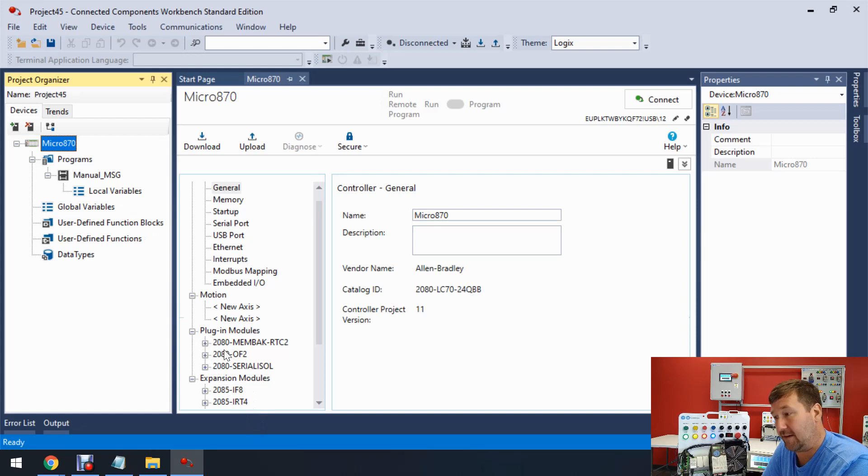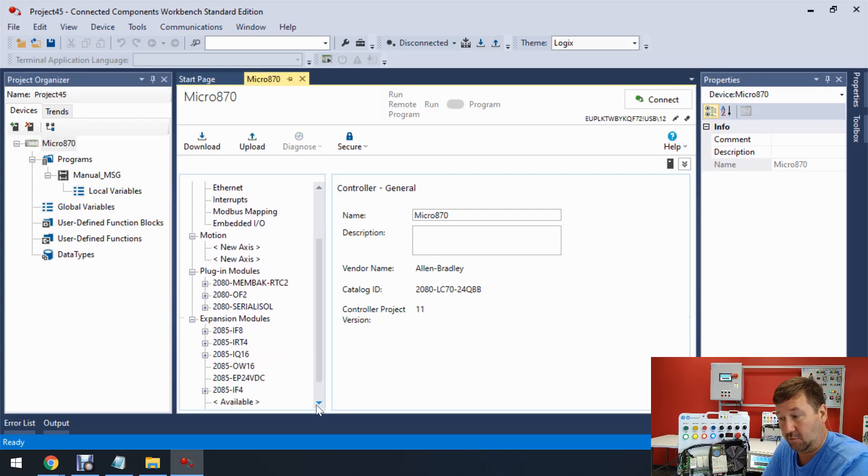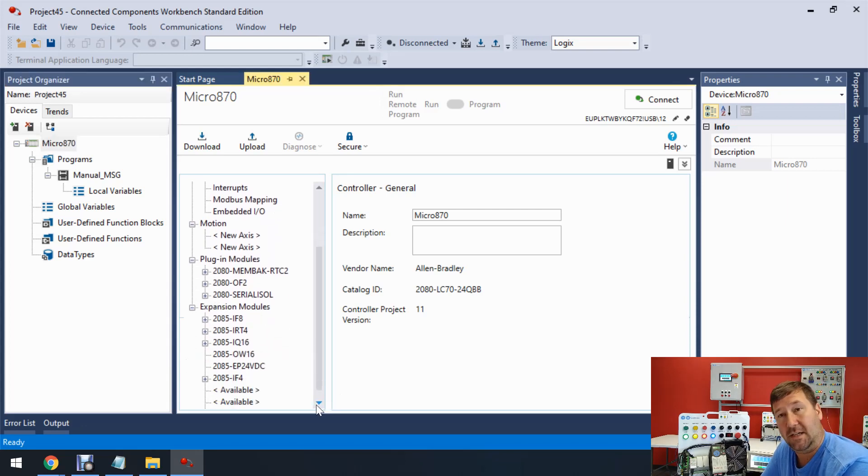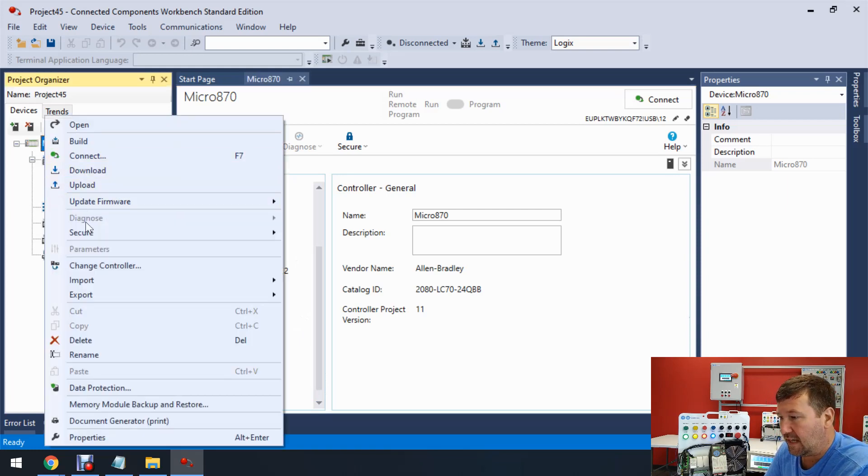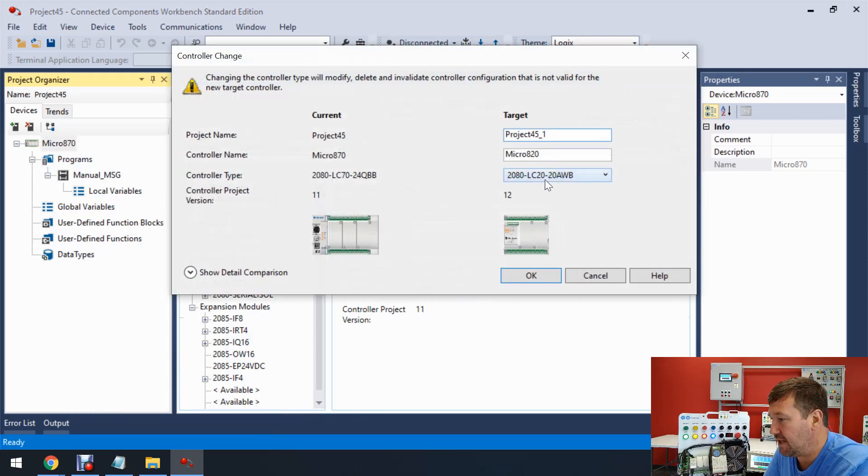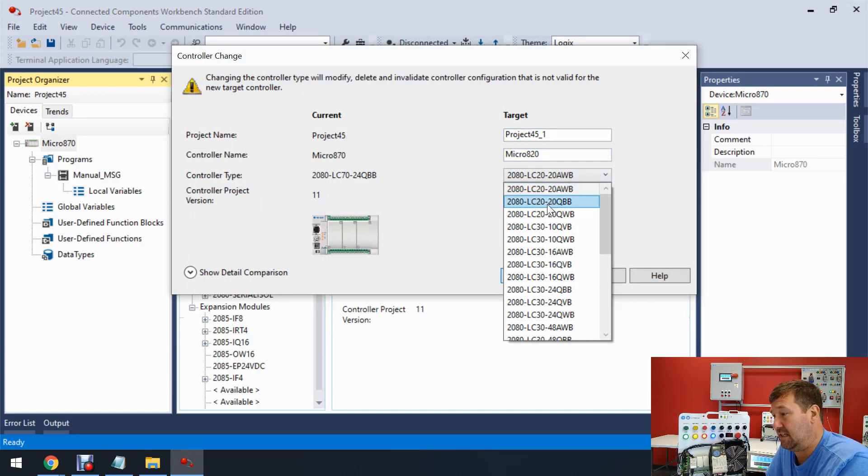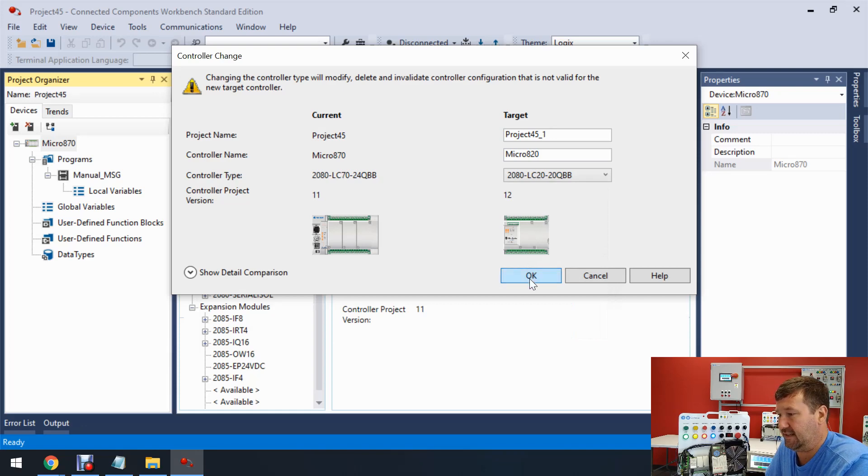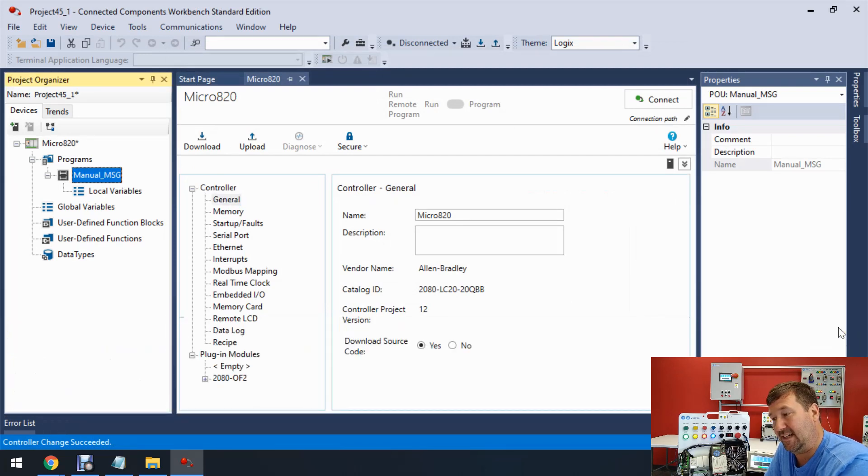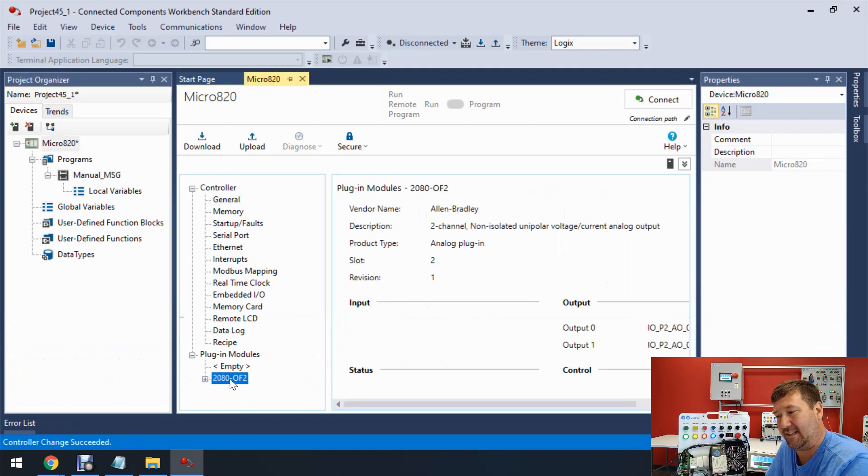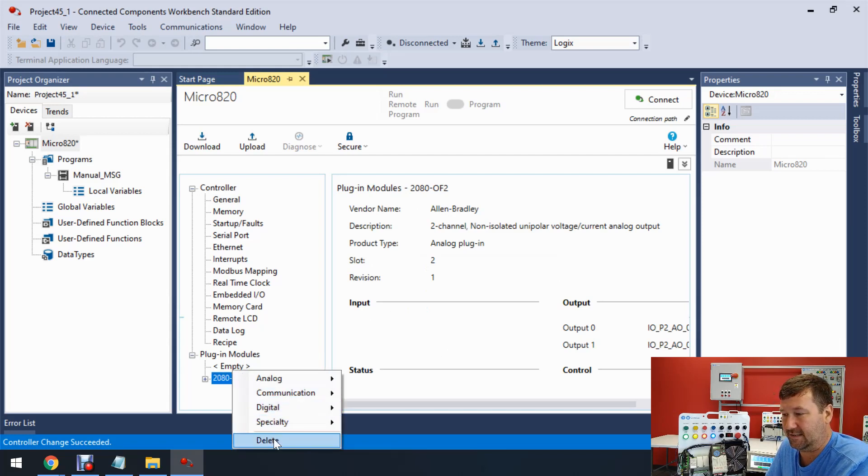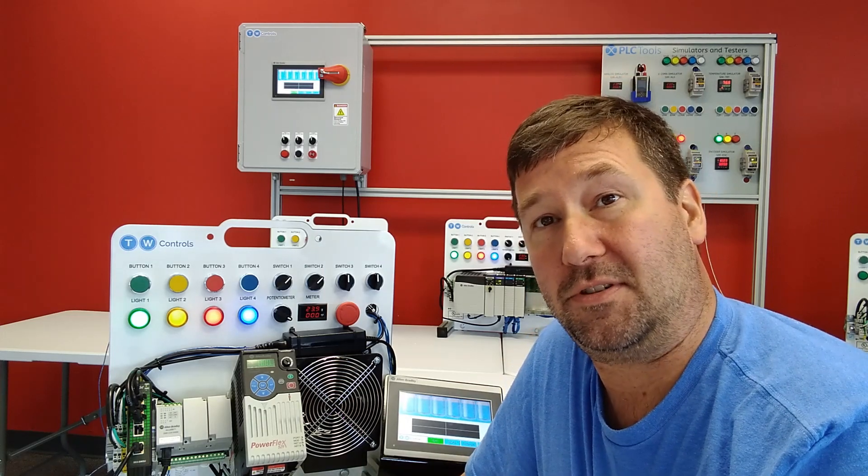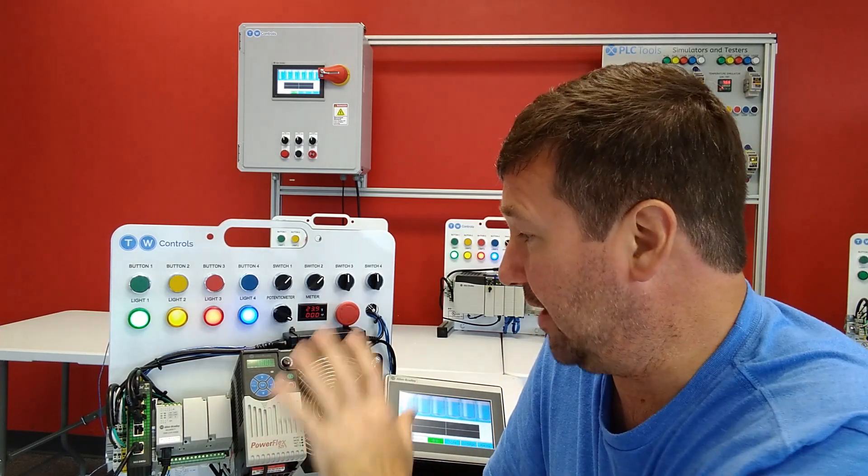So we'll open it up. And there's several things that are different about it. First, they had a very decked out Micro 870 that they were using down here. It had plug-in modules. It had expansion modules. Actually, it was quite a nice setup. We don't have that. We're just using the single 820 here. So first, let's change our controller. So right-click the Micro 870 and click Change Controller. And we're going to change it. In the case of ours, it'll be a 2080 LC20 QBB. We'll select it and click OK. Now, an interesting stumbling block that I ran into the first time is it almost takes all the plug-in modules out. But you see right here, it left this 2080 OF2 in here. So we need to delete it. And the code will still work fine. It was just what they had in their chassis when they were putting this program together.